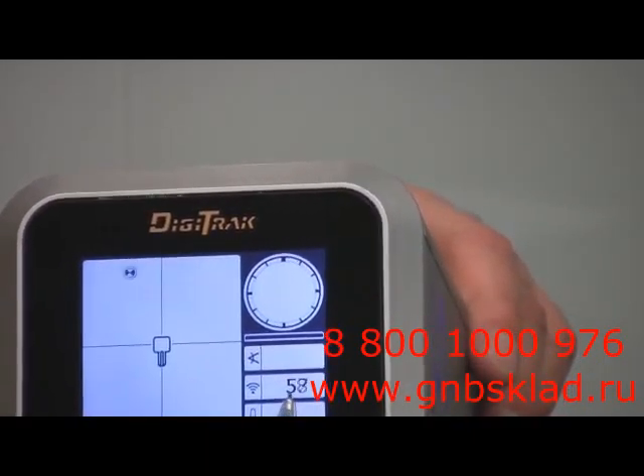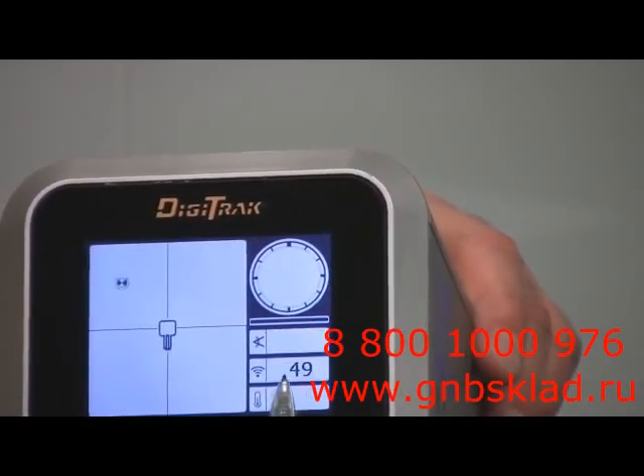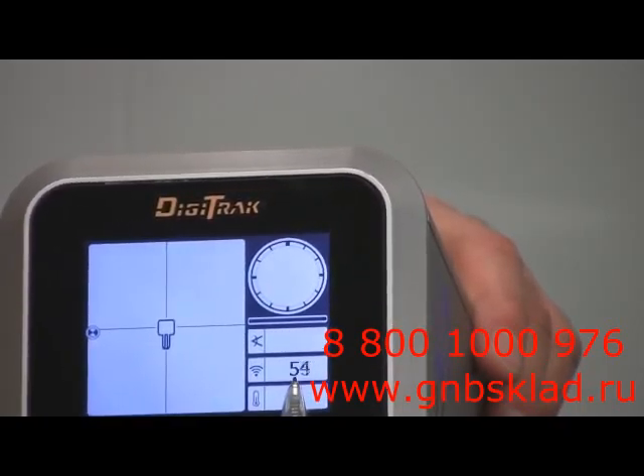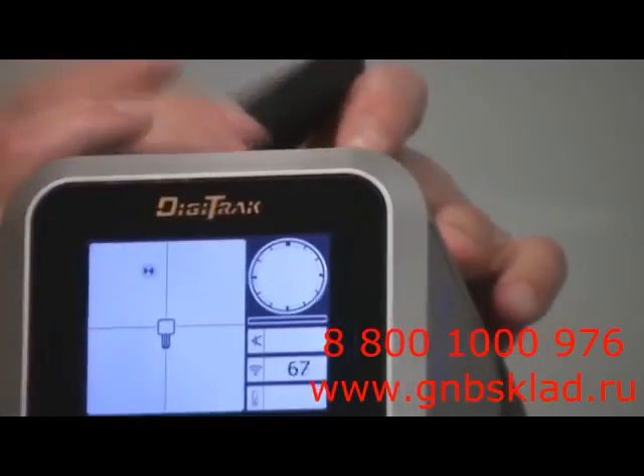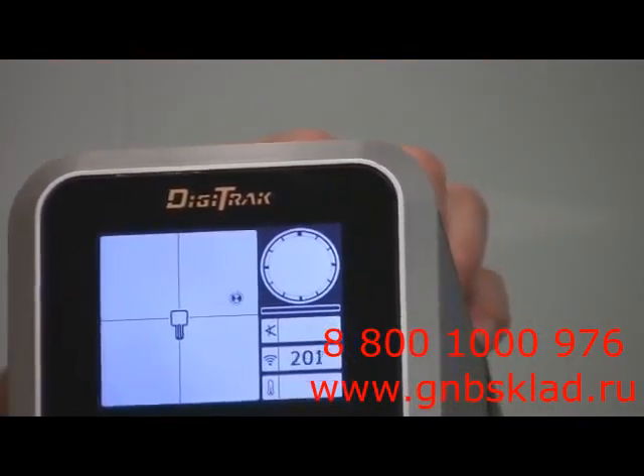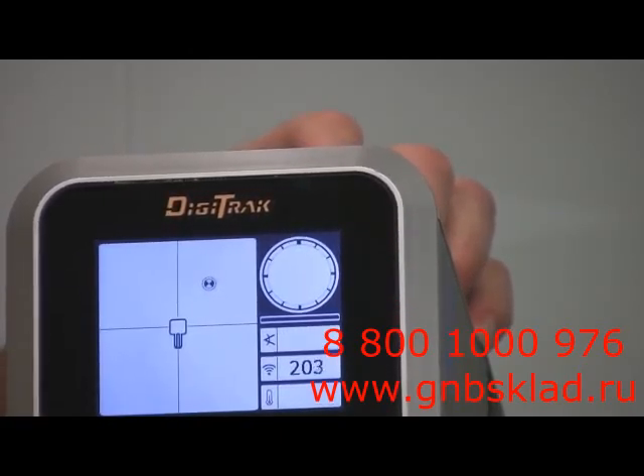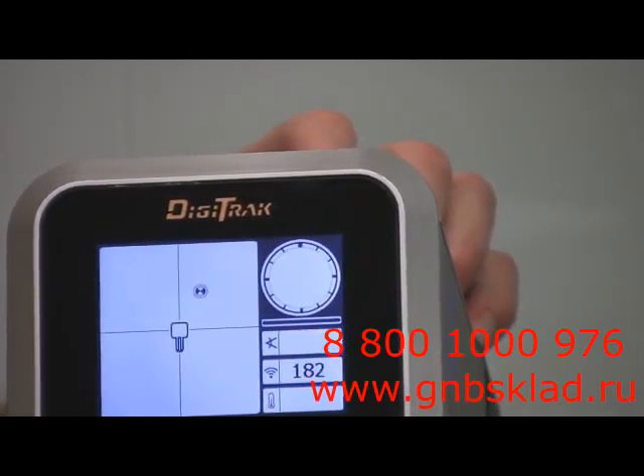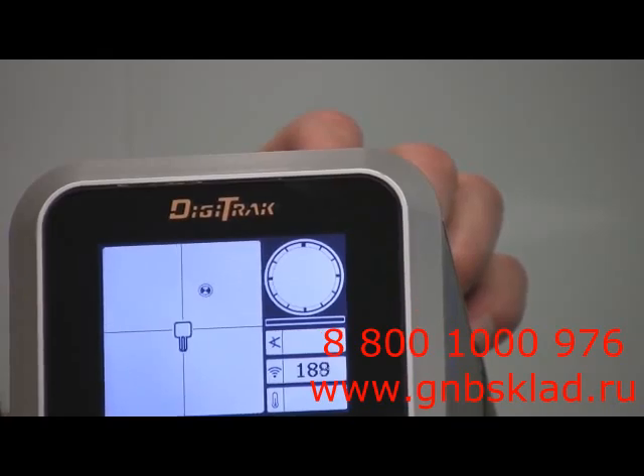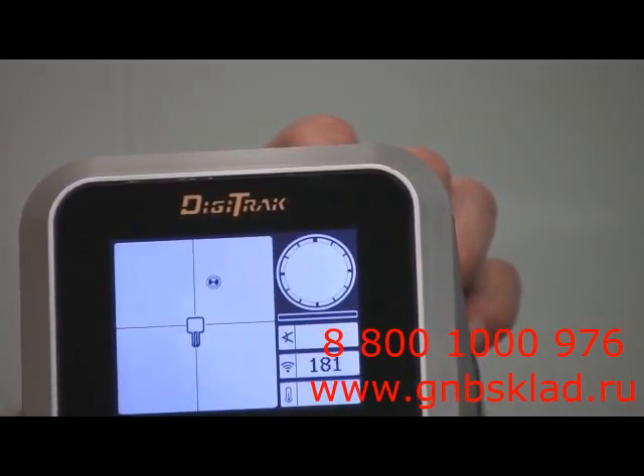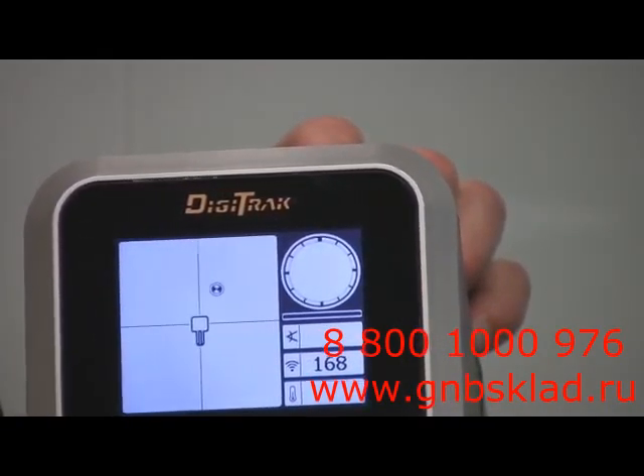So we can see a little bit of signal strength. That's not bad. If I was on a job site, I'd feel pretty lucky if my background noise was that low. But let's throw an interference into the picture. I've now just placed a phone near that. And notice how that signal strength number skyrocketed. That is a very clear illustration of what you're going to see on a job site.